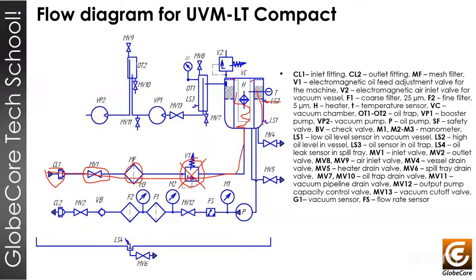And when the oil reaches the sensor LS1 here, the machine knows it can pump out oil from it, and this pump will start to work. When the LS1 is working, pump 1 can work. Then we have here the flow sensor. When this flow sensor is activated, the heater can activate because the machine understands we have flow inside the machine and the oil will not get stuck in the heater.